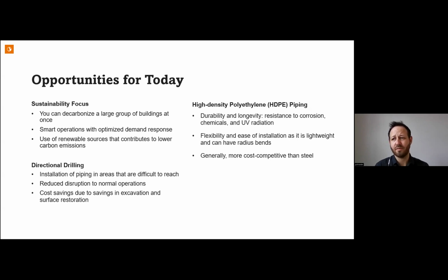The other thing that's really reducing costs for the distribution is changing the pipe type. Steel pipe is still popular for sure. Way back in the day it was concrete, it moved to steel, and now we're seeing high density polyethylene piping. Some of the advantages, as I put here in the slide: longevity and durability, it's very resistant to chemicals and corrosion, and it's lightweight, which really helps with installation. Also, with steel you'd need to put in elbows to make adjustments in the distribution, but with HDPE you can actually do radius turns - so when turning a corner, you don't necessarily need elbows.